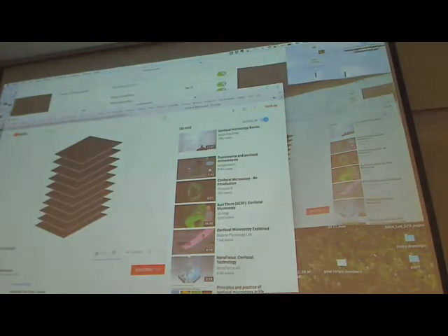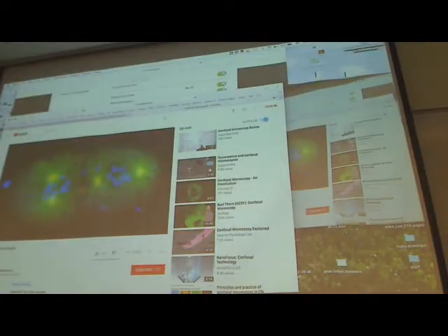The confocal microscope also allows for the construction of 3D images of specimens. Images are captured at multiple planes, ranging in number from 2 to 200, to create a stack of images. Once all the slices are stored in the computer, the image data can be combined computationally to construct a 3D image. As stated earlier, confocal microscopes have the ability to image live specimens.